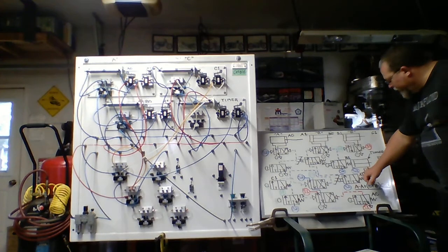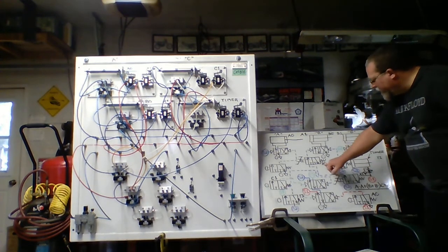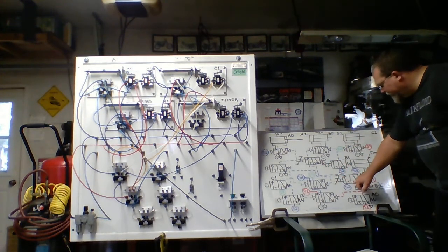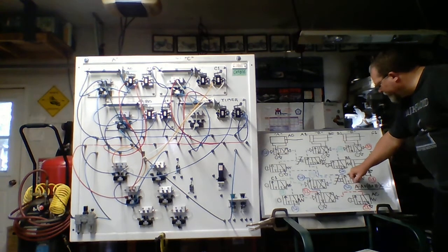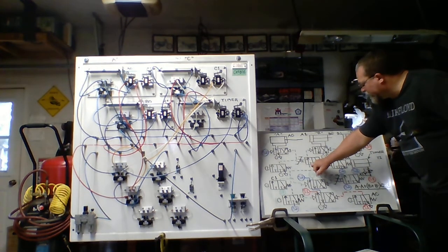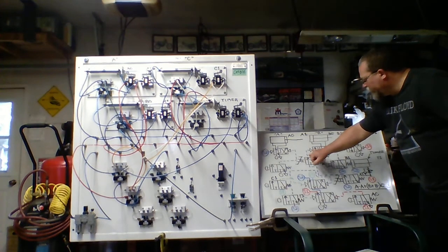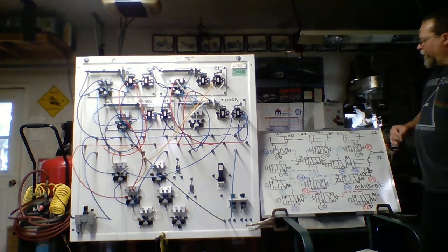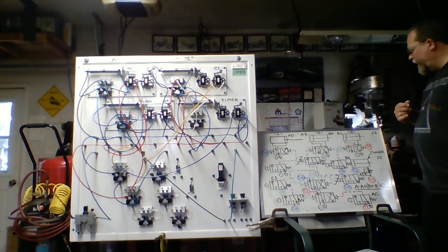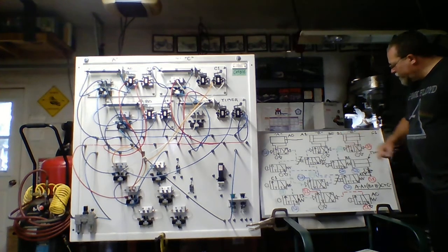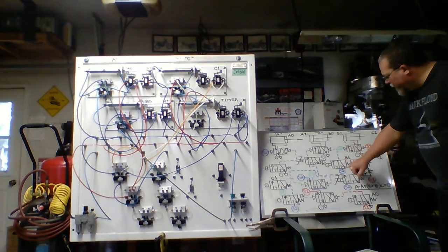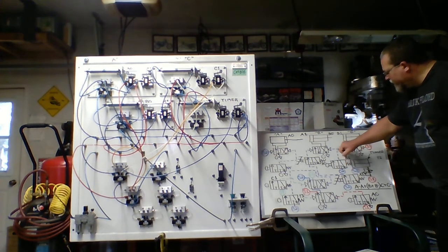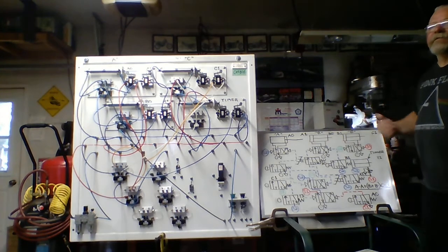So we look at A1, and as I said prior, A1 B0 are set up in series. So here's source 2, plumbed into A1. That will feed into the inlet side of B0, which in turn, because the flow path is open, will pilot the 4 two-way for B to go from left to right, charging the blind end, getting B to extend. Of course, when it extends, it gets on B1. We look at B1 here, and it's tied into source 2 as well. So what will happen, the way this is set up, it'll just continue to reciprocate until, of course, there's a signal to stop it.